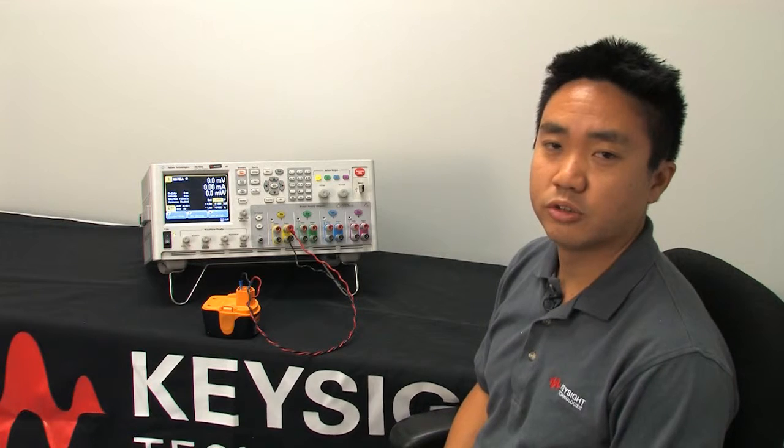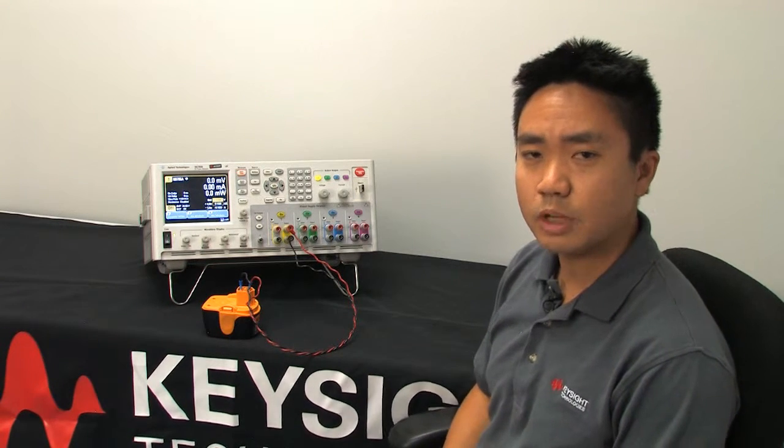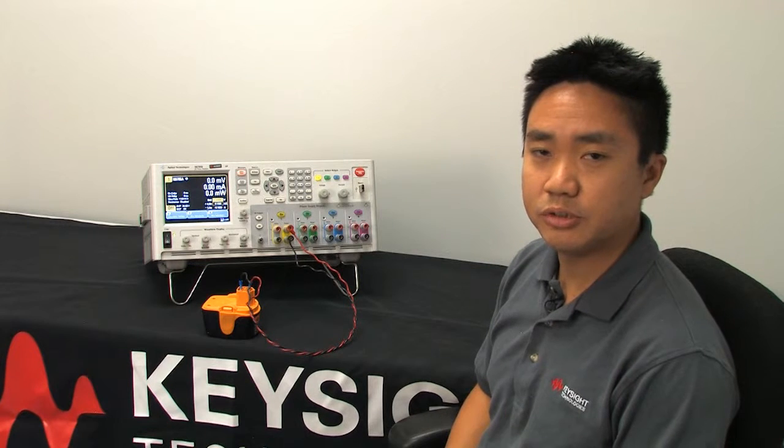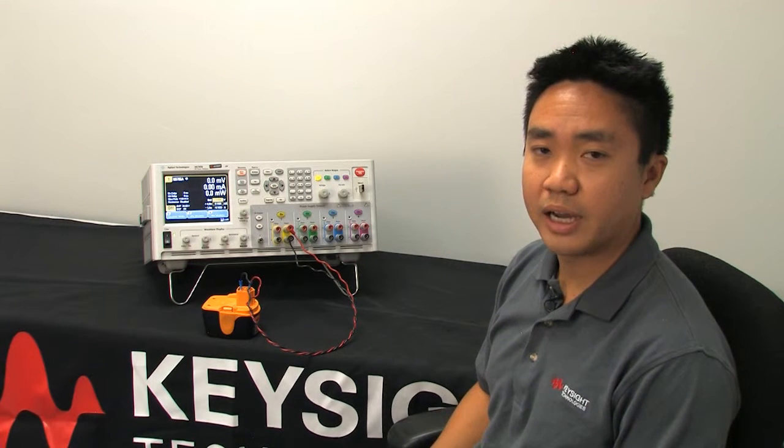One of the key features on our source measure units is the ability to do two quadrant operation. What that means is that our SMUs can act as a power supply and also an electronic load at the same time.